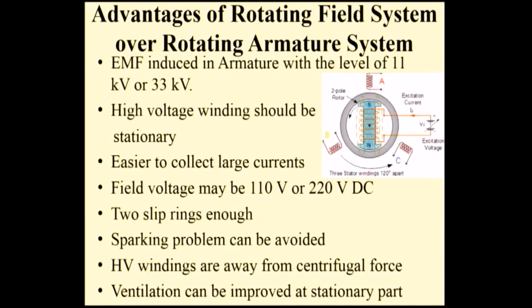The high-voltage winding should be stationary. It is also easier to collect large current if the armature is stationary — if the armature is rotating, collecting electrical energy from it is very difficult. Additionally, the field voltage is normally only 110 to 220 volts. Since the field system is rotating and you are giving only 110 to 220 volts — which is much less compared to 11 kV or 33 kV — it is easy to supply this low voltage to the rotating field system.